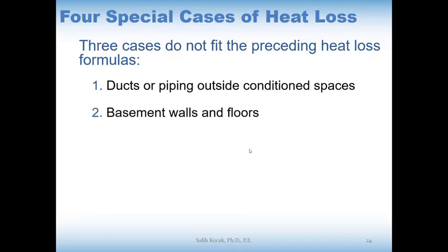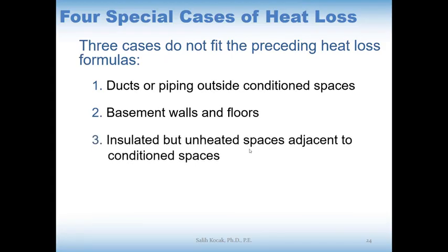Then there are basement walls and floors, and insulated but unheated spaces adjacent to the conditioned spaces, such as a garage. Okay, so it is an insulated but unheated space adjacent to the conditioned space. If you have an attached garage, it is insulated sometimes, most of the time, but it is unheated. Some people want it to be heated, but that's another type of fantasy, to spend more money. Most of the time they are insulated but unheated. That's why this is the other condition.